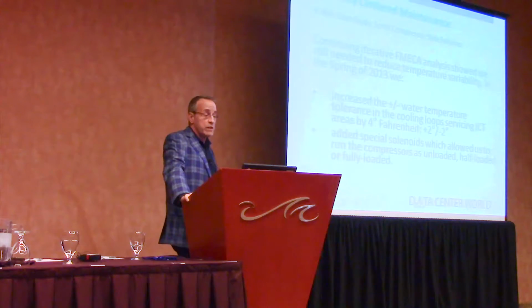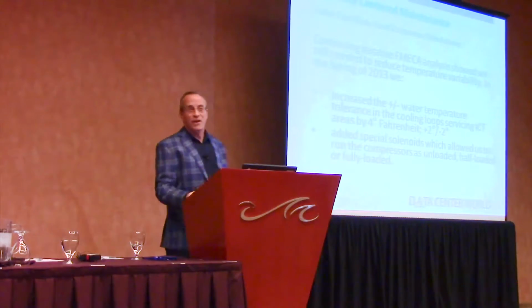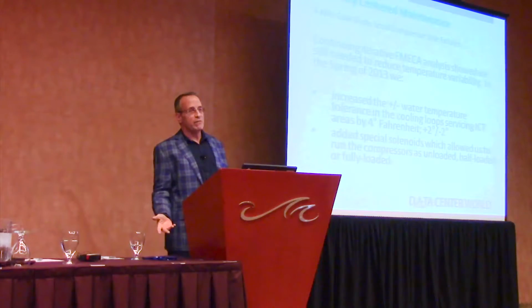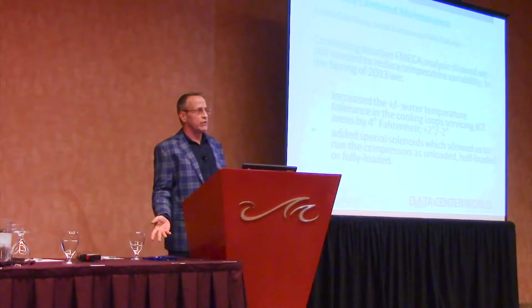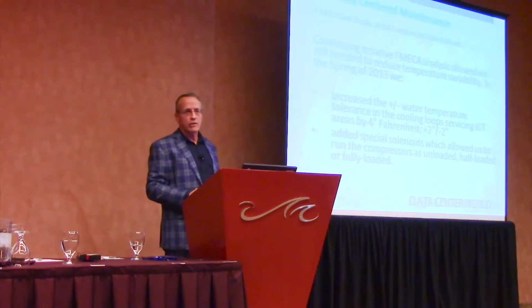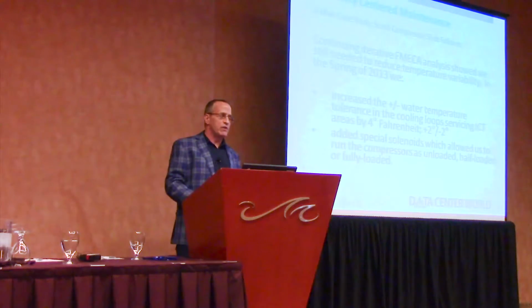Some customers kind of freaked out, and we told them, hey, you don't even want to see the ASHRAE guidelines. And a note on that, we run the intake temperature towards the bottom of our cabinets at 68, 69 degrees on a slab, and the intake temperature at the top, 71, 72. We all know with the new ASHRAE guidelines and modern computing equipment, we can go much higher.